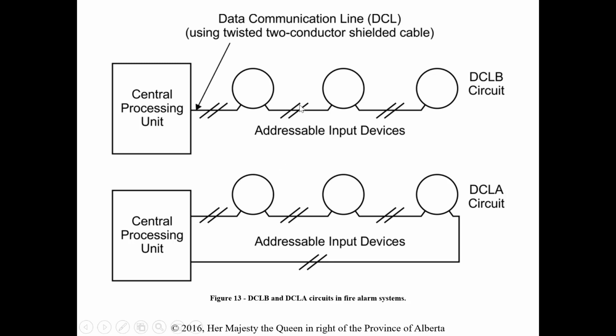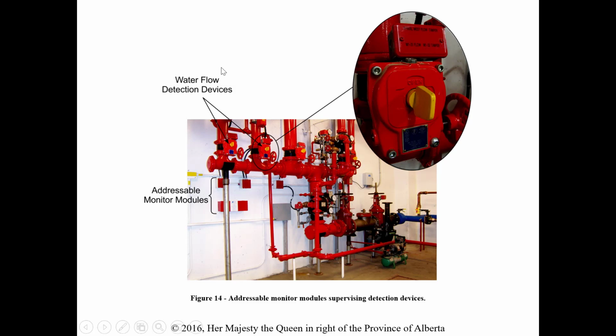Again, we have some scenarios we've talked about where we're not allowed to do splices. We'll address that here coming up, because once we have an addressable scenario, it's a bit of a different situation. Because those devices are talking back all the time, we're not so worried about removing a device and the rest of it working. We'll go through that here coming up too.